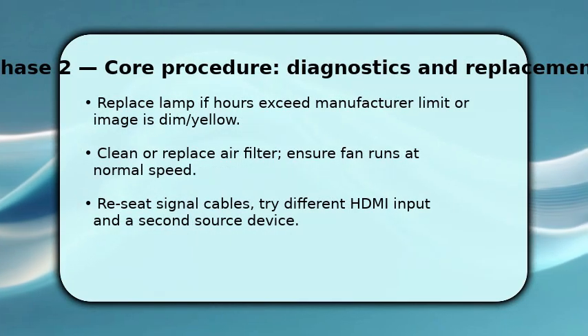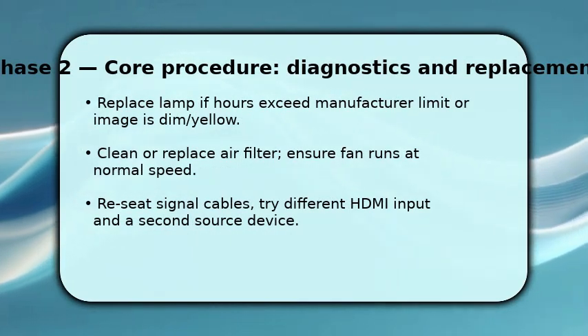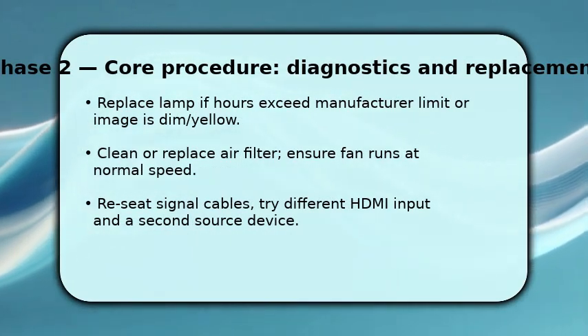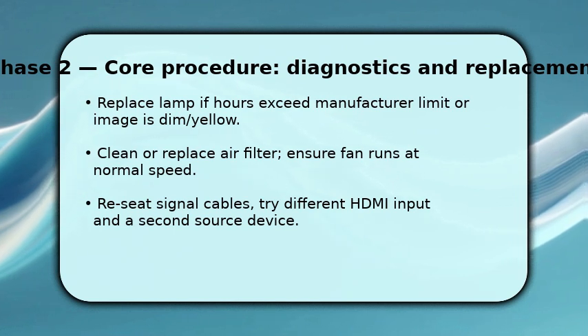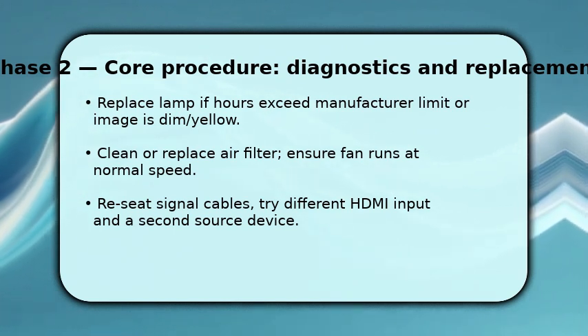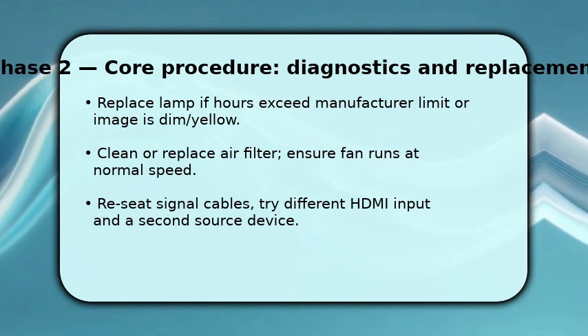Now focus on lamp and signal problems because they explain most image faults. You should replace the lamp when hours exceed the limit or colors shift toward yellow. A new lamp restores brightness and color balance.